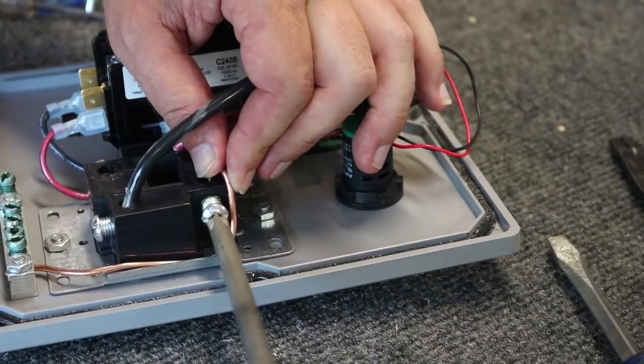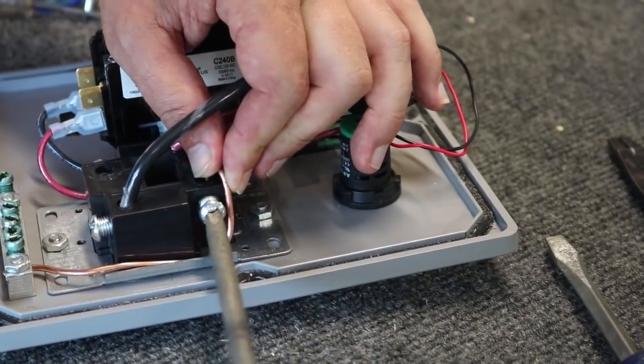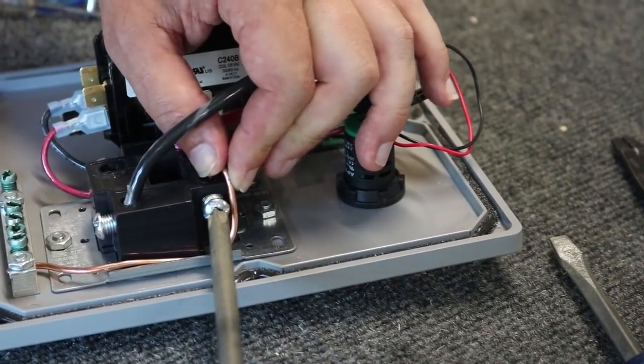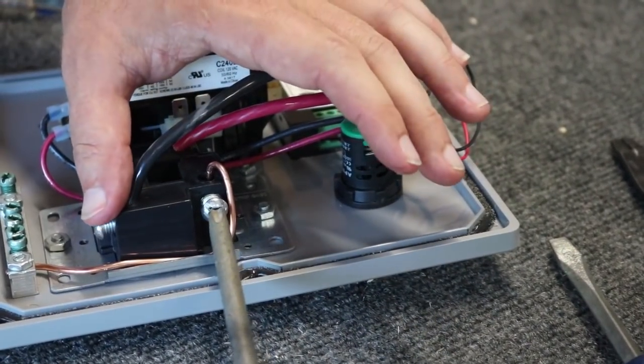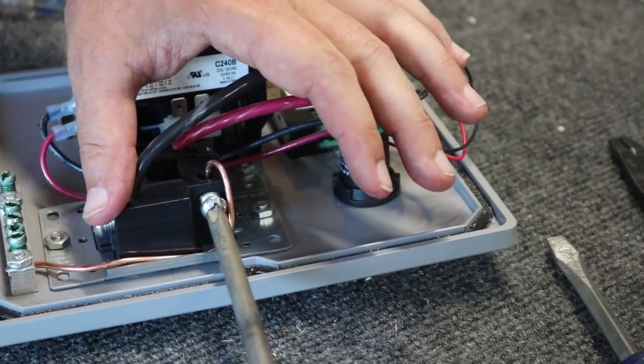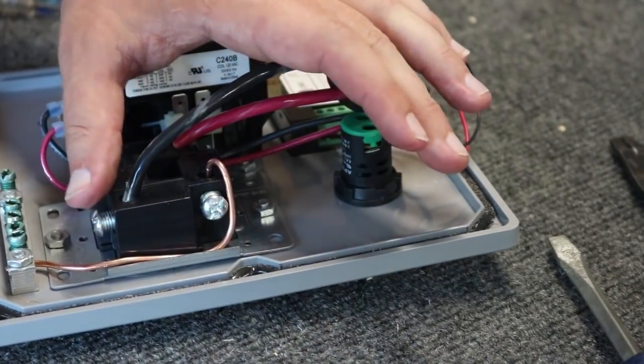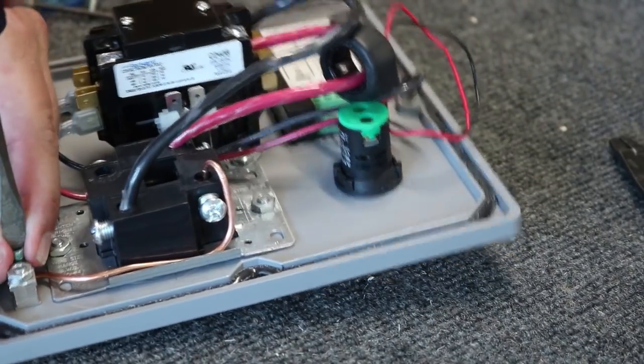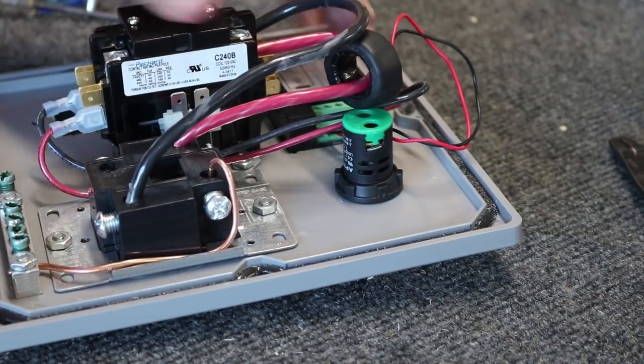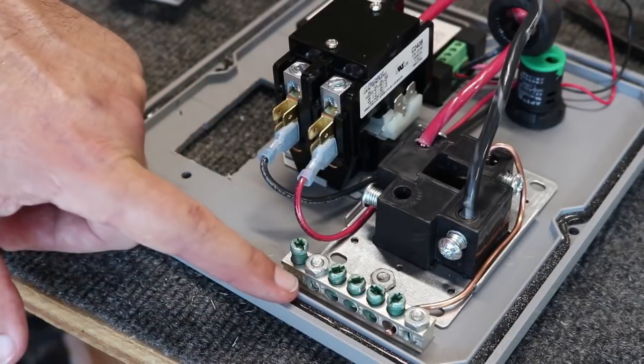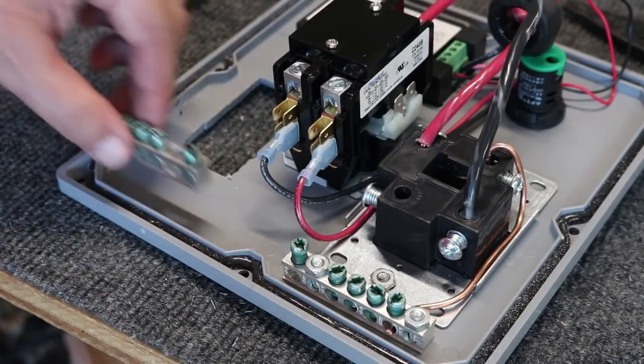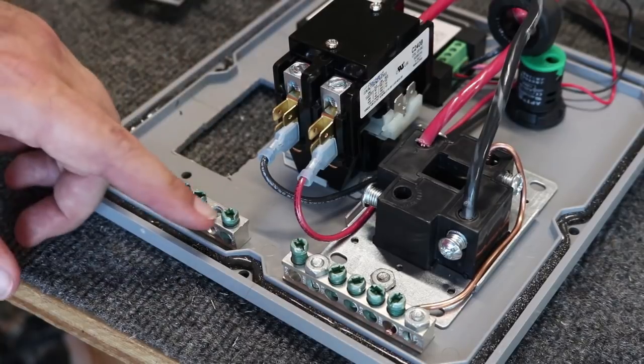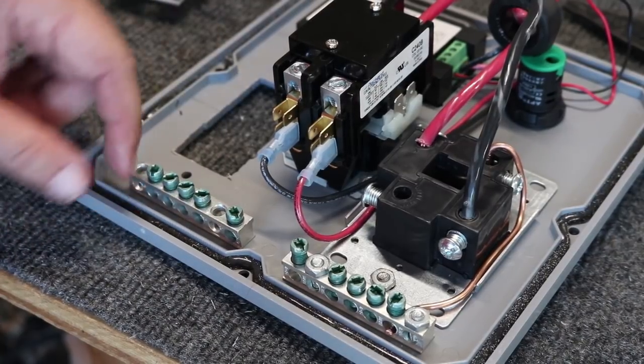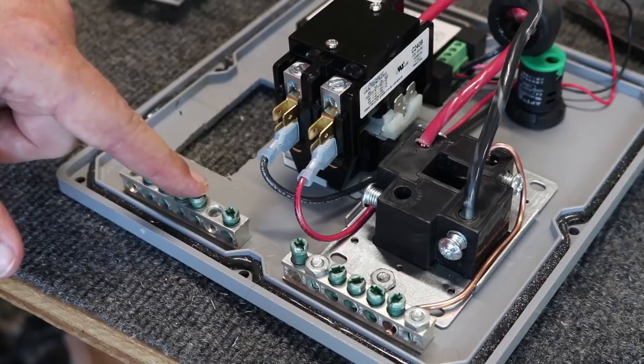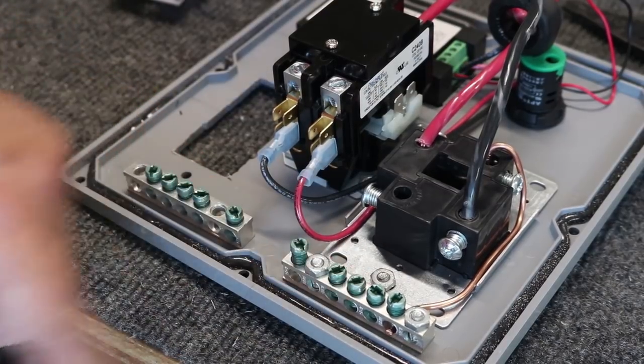Next, I'm adding the ground to the NEMA 14-50 outlet. This is a heavy gauge wire and it's solid, so I pre-bent it with the pliers to make a shape that fits here, and then tighten down the connector on the outlet and the ground bus bar. So here's the installed ground bus bar. I'm also over here going to add a bus bar for all the neutral connections. So I'll mark those, drill them, and bolt them down just like I did for the ground bus bar.